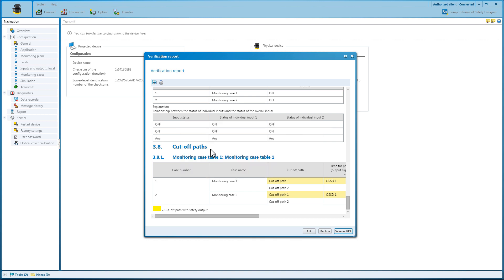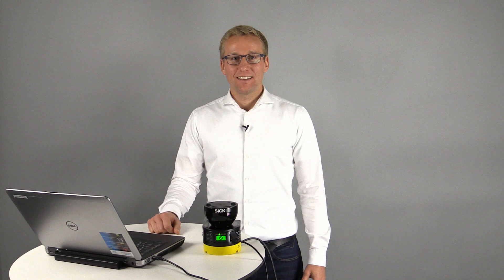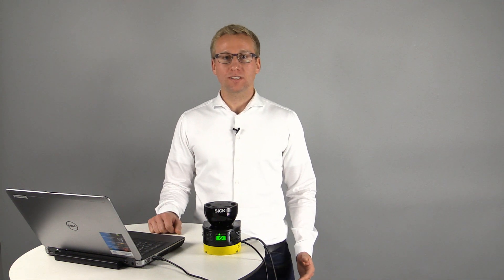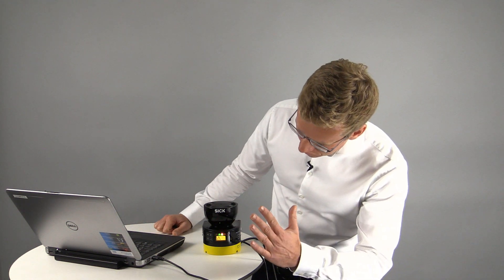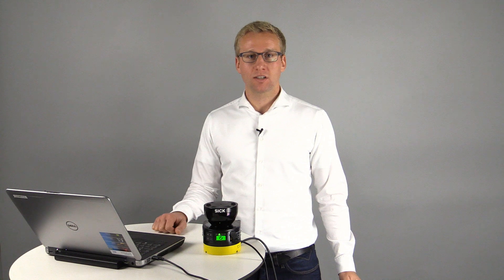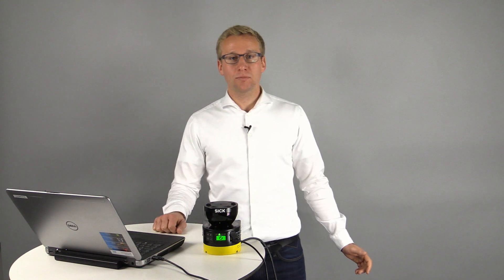We'll transfer the configuration to the safety laser scanner. The multi-color display of the Microscan 3 shows the current status of the device very clearly and even from long distances. Infringing a warning field can trigger a signal lamp for example; however, it does not lead to a safe machine stop. If the protective field is infringed, the machine immediately stops safely.